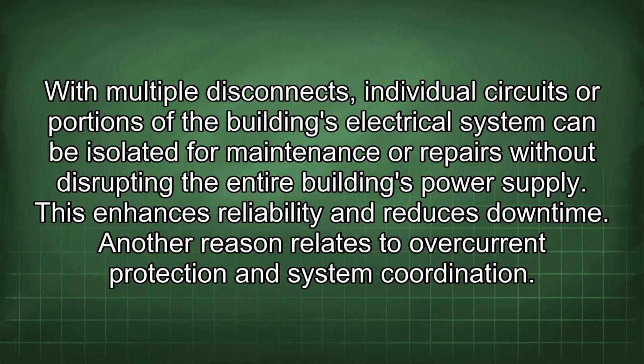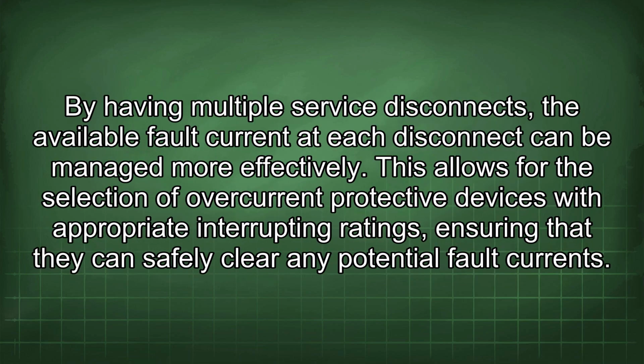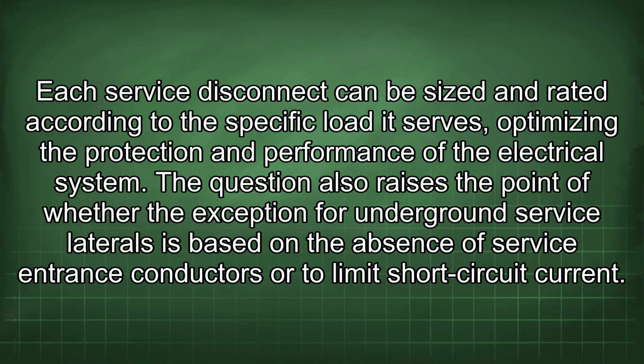Another reason relates to overcurrent protection and system coordination. By having multiple service disconnects, the available fault current at each disconnect can be managed more effectively. This allows for the selection of overcurrent protective devices with appropriate interrupting ratings, ensuring that they can safely clear any potential fault current. Each service disconnect can be sized and rated according to the specific load it serves, optimizing the protection and performance of the electrical system.